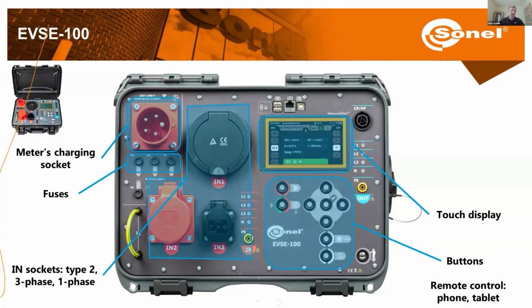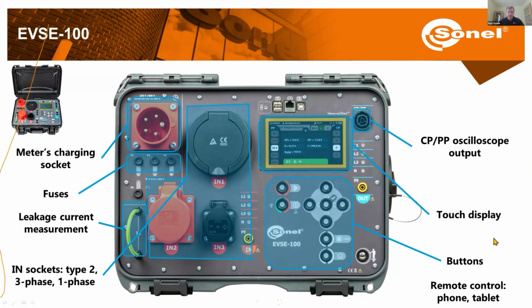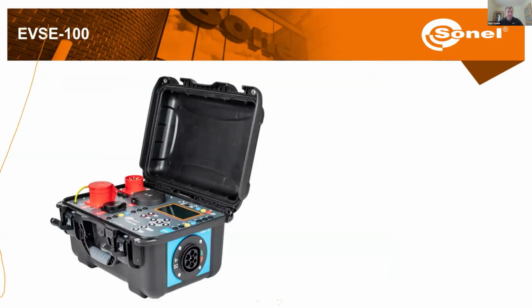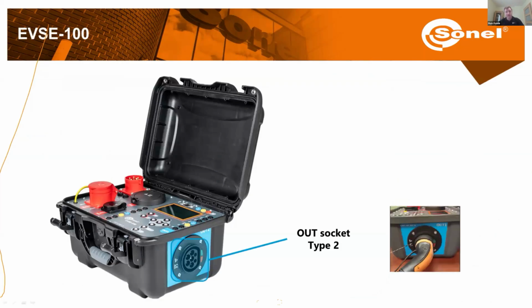Now here are the in sockets, and this is a single phase, three phase, or a type 2 socket. The out socket is on the side of the meter. And further, for leakage current measurements, we have an additional wire here on which we can put a clamp multimeter to check leakage currents. Here is an additional socket for communication with an external oscilloscope, and for communication with a computer we have USB sockets, LAN cable, or some other additional USB sockets, for example, for a thumb drive or a barcode printer and scanner. Okay, here on the side this is an out socket, and this is a type 2 socket.